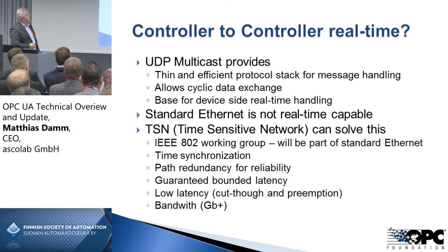And so this is for controller real time. The idea is not to have a new field bus defined. The focus is on controller communication, and there are a lot of use cases where you also need real time on the controller communication, and there is no solution on the market today. You can say, okay, there is Profinet, EtherCAT, PowerLink, whatever, but there's not one standard that's supported by all of the vendors. So there is no interoperability solution on the market today, and the goal is to close this gap for controller communication.